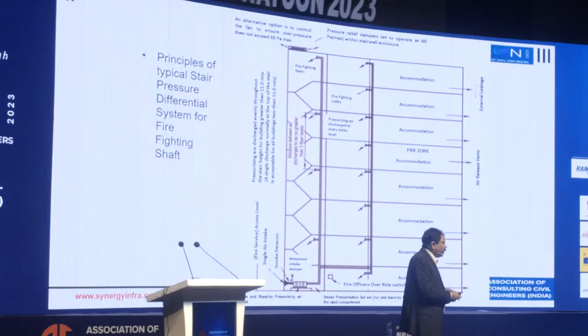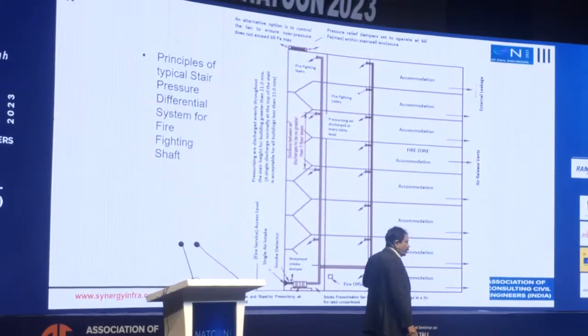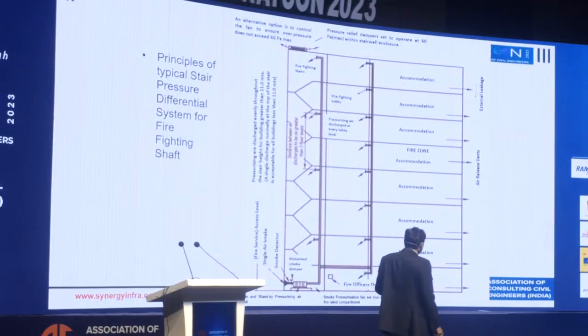If you have a fan at the top and fire or smoke is coming up, it may pick up the smoke and put it back into the shaft. That's why you need a fire damper as well as a smoke detector, so that the shaft is properly protected.